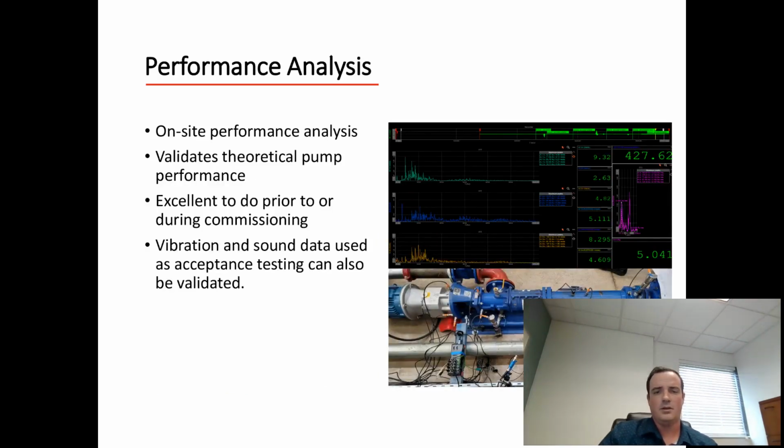Okay, so next I'm going to speak a little bit about performance analysis. This is an on-site service that we offer. Oftentimes you'll see in bid specs or things like that, the need to validate a pump's performance. What we've been offering and have the capability of doing is a true on-site performance analysis of a pump. We can validate against theoretical curves and tell the customer that indeed their pump is operating as intended. This is excellent to do during commissioning or startup. And lastly, we can also gather vibration and sound data for validation and acceptance as well.